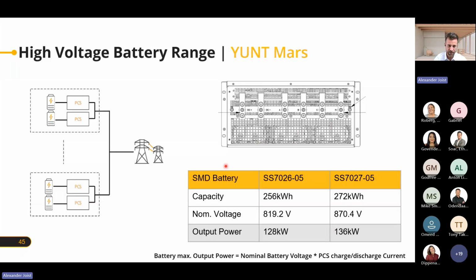So now here also the calculation again, like we did earlier for our systems. With the 125 kilowatt PCS, we need a minimum of 256 kilowatt hours of battery. So nearly the biggest battery. So only 16 modules is the minimum we should run with this PCS, with a 125 kilowatt PCS. But I mean, if you know the client only has 80, 90 or 100 kilowatt loads and not higher, you could obviously also do it a little bit lower just to save some cost, but then we must make sure he doesn't overload the system.